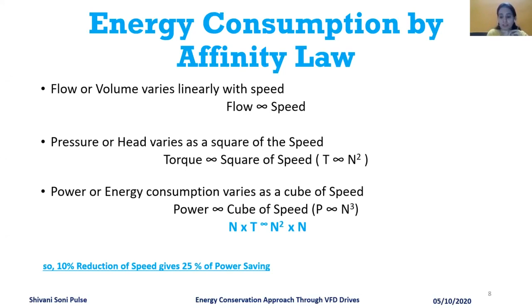The power or energy consumption varies as the cube of the speed of the motor, so we can say that a 10% reduction in speed gives a 25% saving in power consumption. Here we can see in the graph that flow is linearly proportional to speed, the pressure varies as the square of the speed, and the power consumption as the cube of the speed.